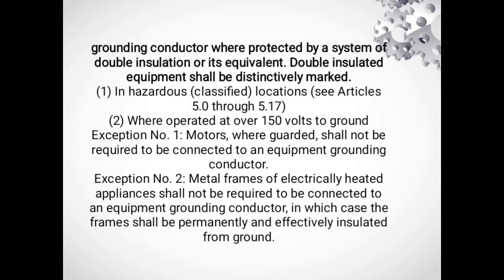Number 1. In hazardous locations, Article 5.0 through 5.17. Number 2. Where operated at over 150 volts to ground. Exceptions to number 1: Exception number 1, motors where guarded shall not be required to be connected to an equipment grounding conductor. Exception number 2, metal frames of electrically heated appliances shall not be required to be connected to an equipment grounding conductor, in which case the frame shall be permanently and effectively insulated from ground. Bonding special cases: separately derived systems like a generator need their metal parts and piping bonded to their own grounding system, then tied into the building ground. This ensures grounding consistency across all power sources.